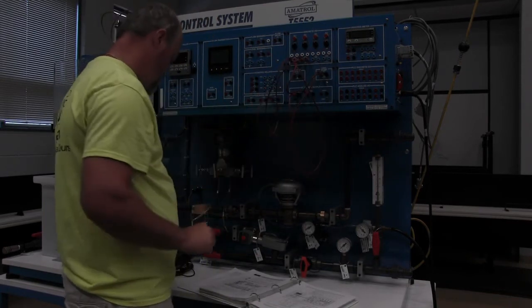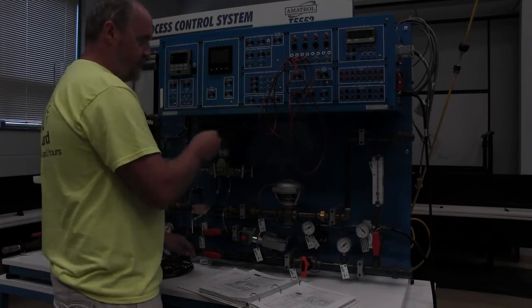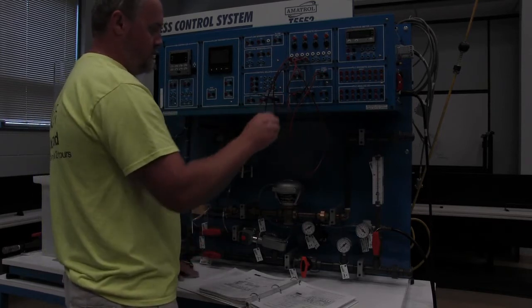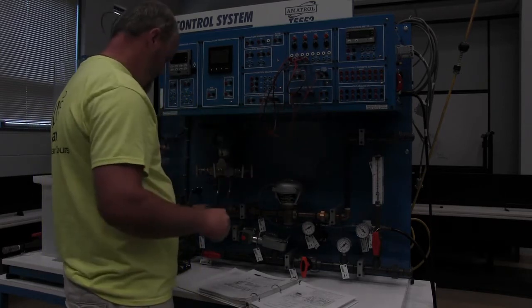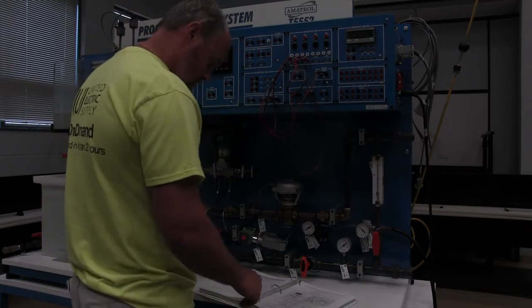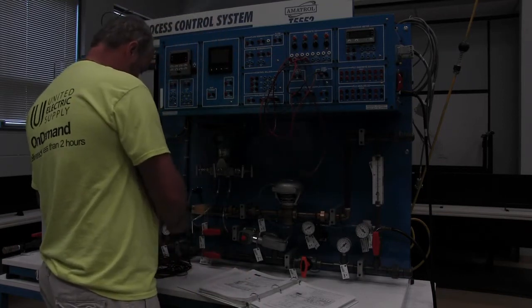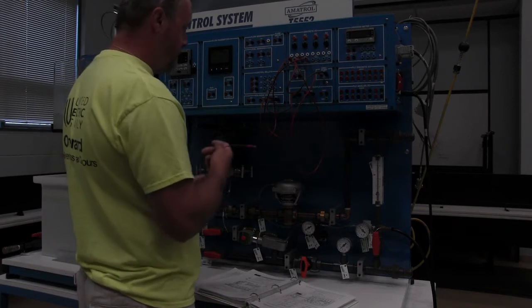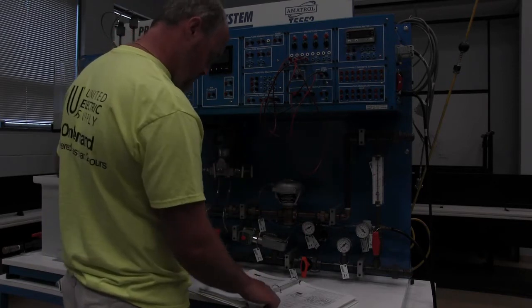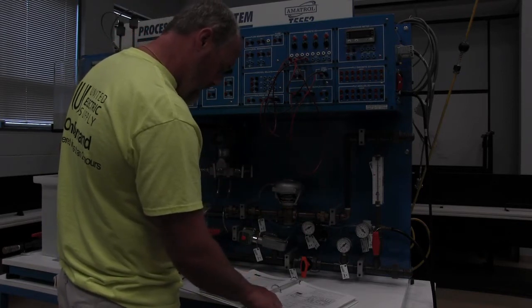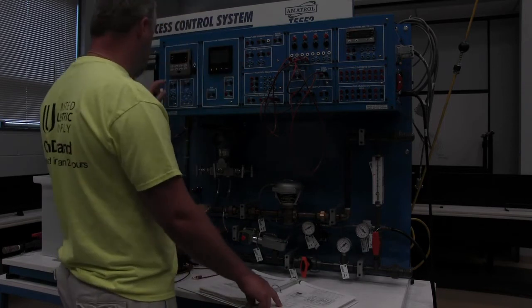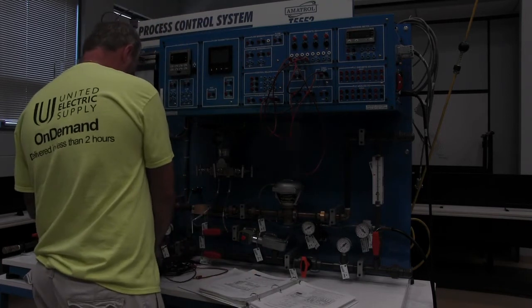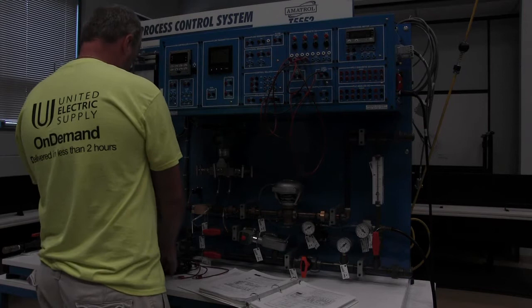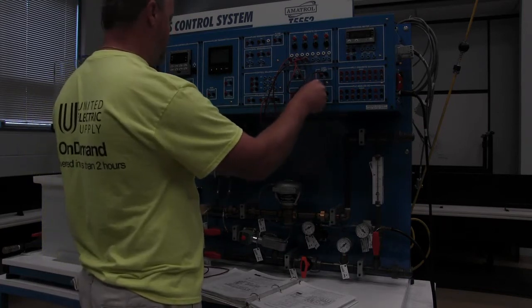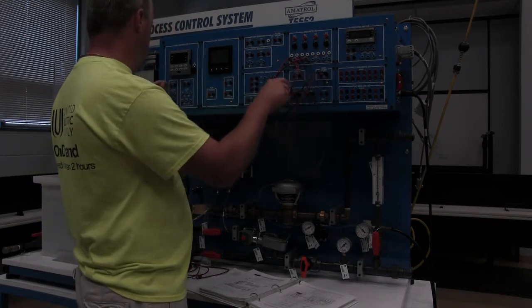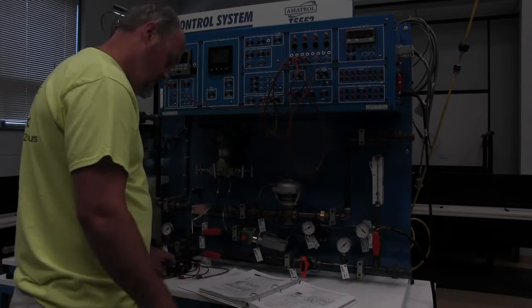Solenoid valve 3. From the negative of solenoid valve 3, we're just going to take that back to the negative of the power supply. And from the plus of the 24 volt power supply, we're going to go to the AI1 controller inputs, which is over here. Need a little bit longer for that. All right, so we're going to go from a 24 volt, just piggyback the AI1.